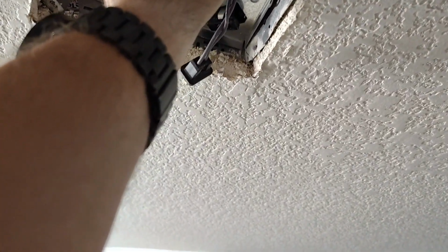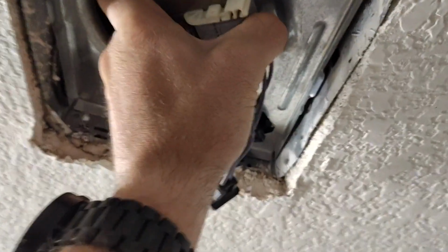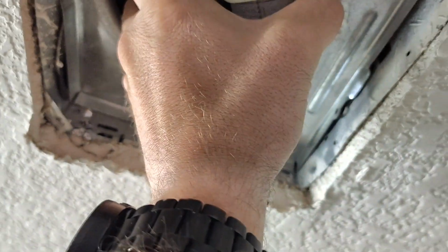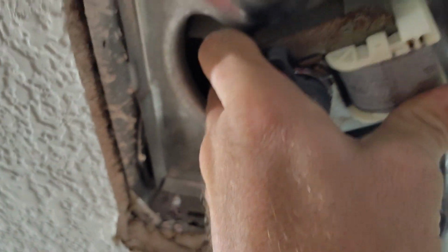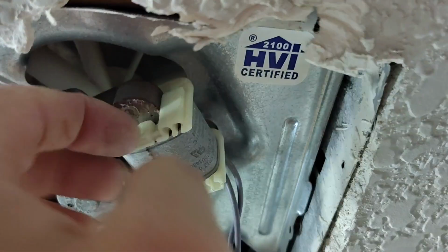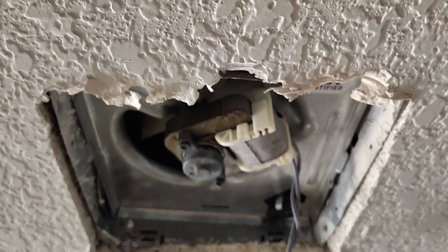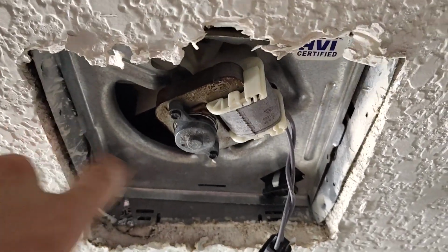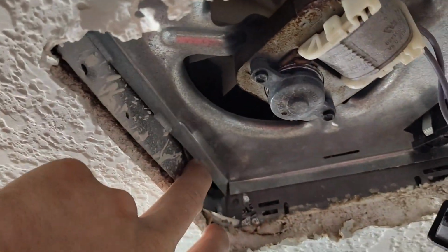And then typically, these will just pull out of there. Sometimes they do something funky to screw it in place, which it looks like they may have done here. But a lot of the times it's just held in by these clips. But, let's see, yep, they got some screws in here I'm going to have to remove. That'll pull your motor out, and then we'll just have to remove this trim box and this ductwork.